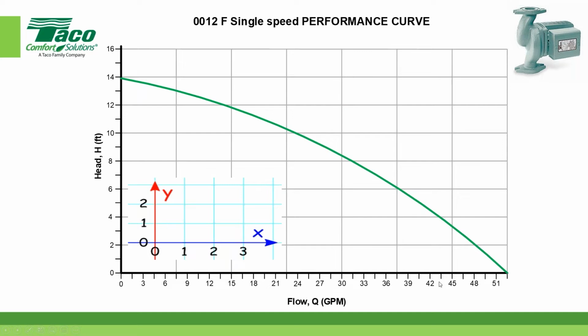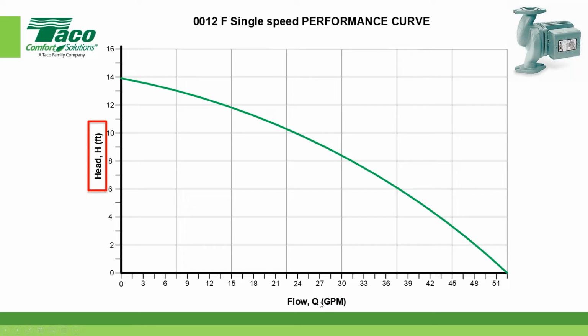And out here we have the x-axis, okay? Within that, we have feet of head and flow. Flow first and then feet of head. The reason I did it that way is you can't ever know what the resistance of the system is until you get a certain amount of flow. The letter Q will represent that in some cases, and it goes back to an ancient language, but it's where we get the word quantity, okay? So I believe it's Latin. And then over here, head, or height, is a way to understand what H stands for as well.